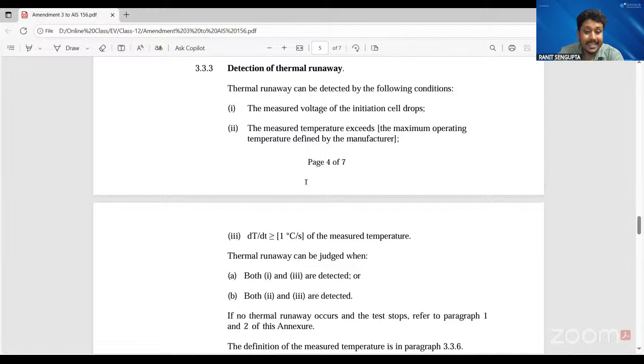Third point is dT/dt, the rate of change of temperature with respect to time. That should be greater than or equal to 1 degree centigrade per second. The temperature rise on the thermistor, the temperature sensor applied on the cell surface, means the inside cell temperature should be increasing at a rate of 1 degree centigrade per second. Now you can see how thermal runaway can be judged.